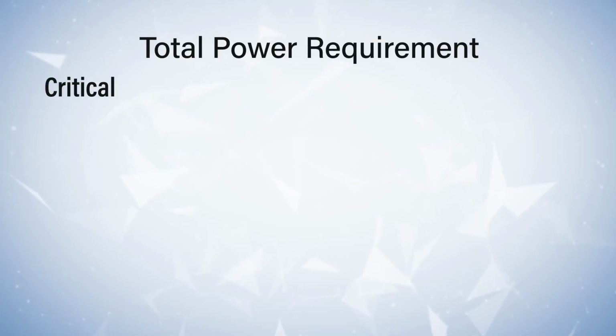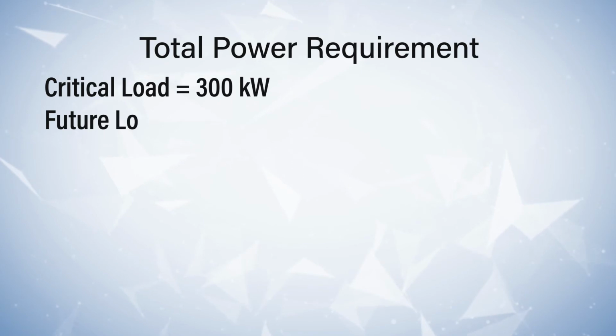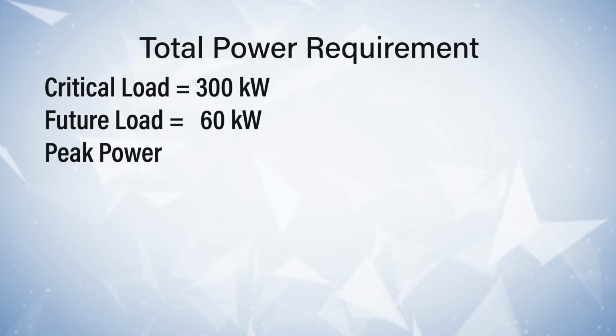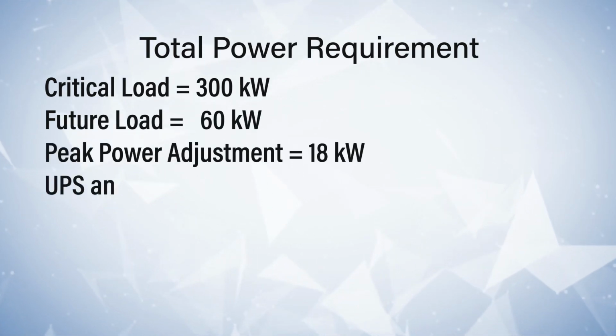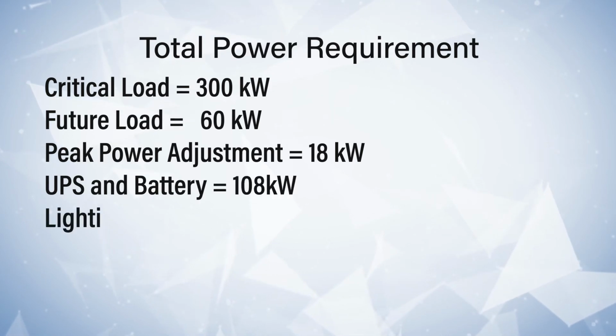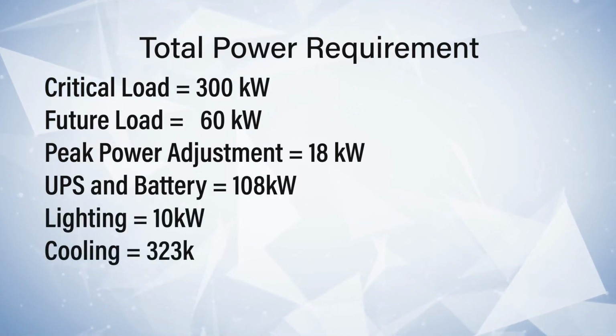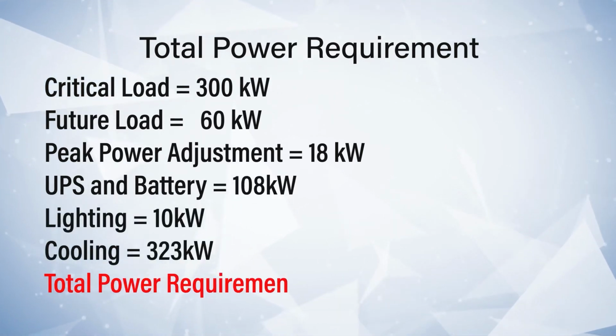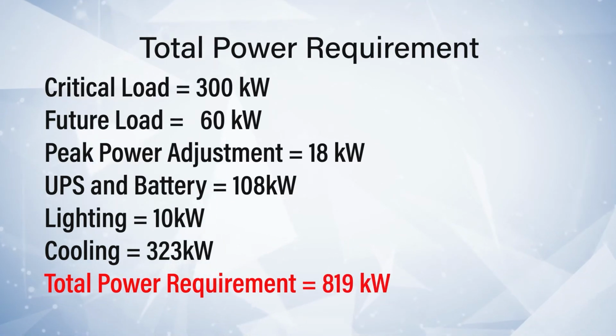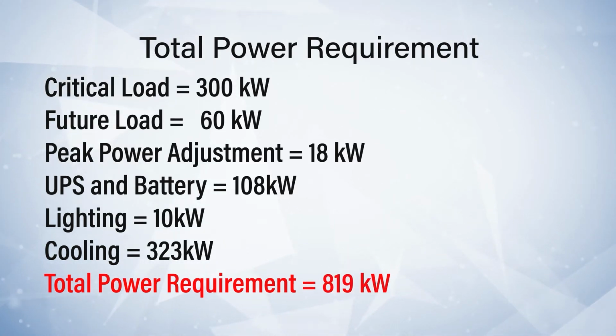Now we have done our calculation. Let us look at the total power requirement of our data center. So our critical load is 300 kilowatts, future load is 60 kilowatts, peak power adjustment is 18 kilowatts, UPS and battery is 108 kilowatts, lighting load is 10 kilowatts, cooling load is 323 kilowatts. So total power requirement is 819 kilowatts.